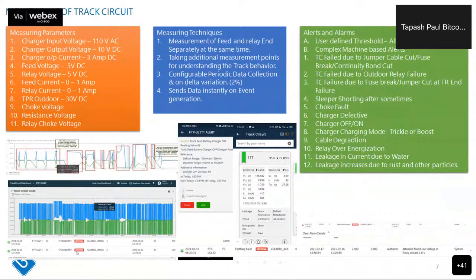Some of the alerts and alarms in these track circuits are user-defined thresholds. The user knows how the system works and in which voltage range it works better. So the user can define the threshold, for example, that the charger input should be 90 volts: if it is less than 90 volts I should get an alarm, or if it is more than 125 volts I should get an alarm.